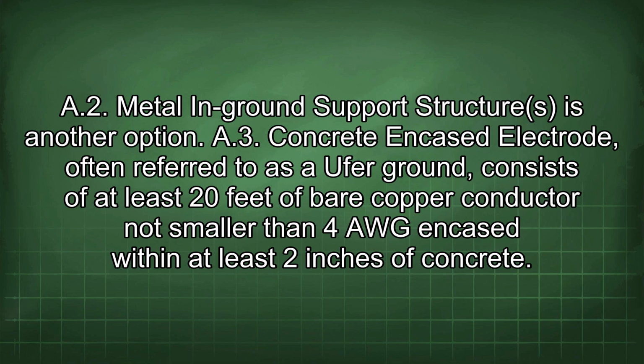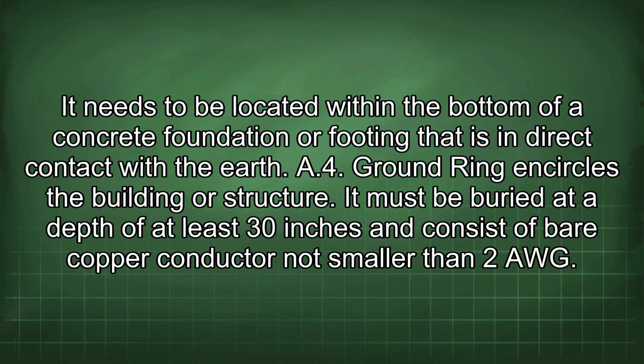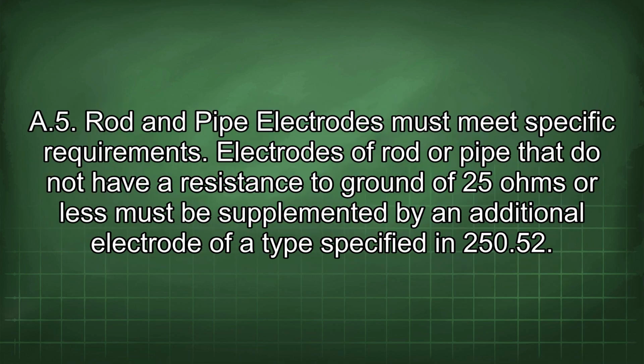A2. Metal in ground support structures is another option. A3. Concrete encased electrode, often referred to as a Ufer ground, consists of at least 20 feet of bare copper conductor not smaller than 4 AWG encased within at least 2 inches of concrete. It needs to be located within the bottom of a concrete foundation or footing that is in direct contact with the earth. A4. Ground ring encircles the building or structure. It must be buried at a depth of at least 30 inches and consist of bare copper conductor not smaller than 2 AWG. A5. Rod and pipe electrodes must meet specific requirements.